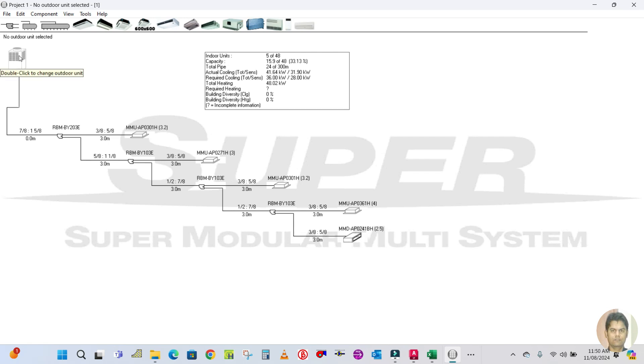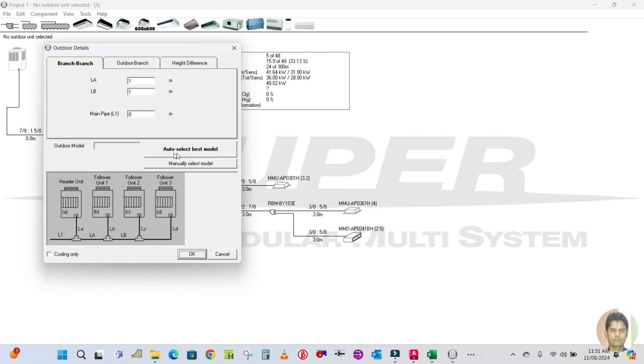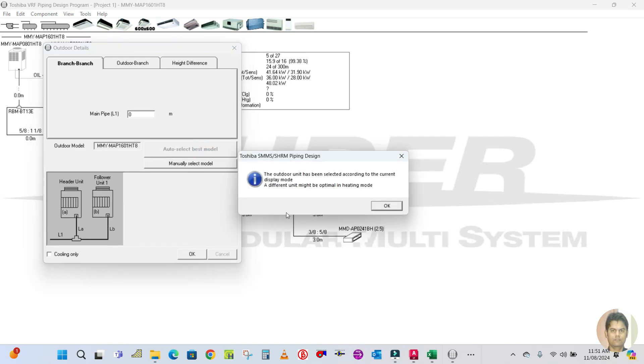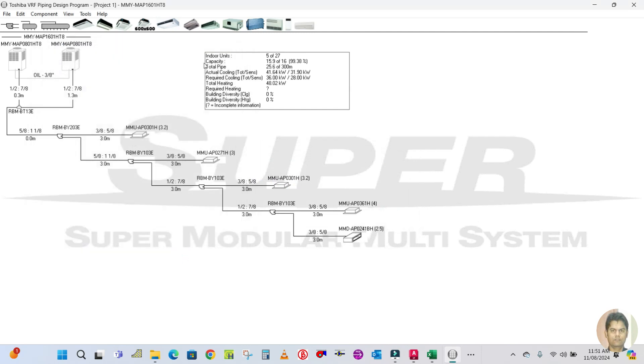Double-click here to configure the outdoor unit. You can see the auto-select best model option — I don't want to select manually; I want the software to select for me. Double-select the model and click OK. You can see: number of indoor units is 5, maximum is 27; connected capacity is 15.9 kilowatts; total pipe length is 25.6 meters, maximum is 300. The indoor unit is 8 HP, 2 units, total 16 HP.